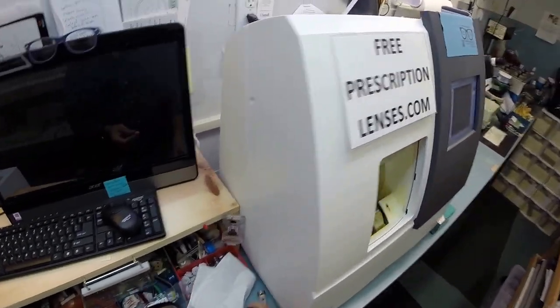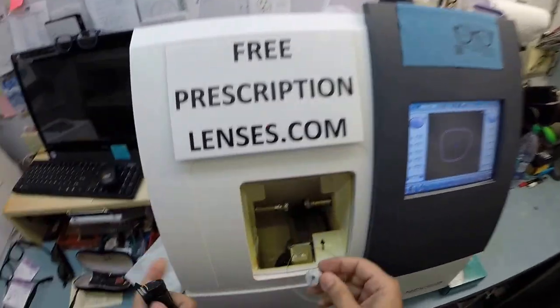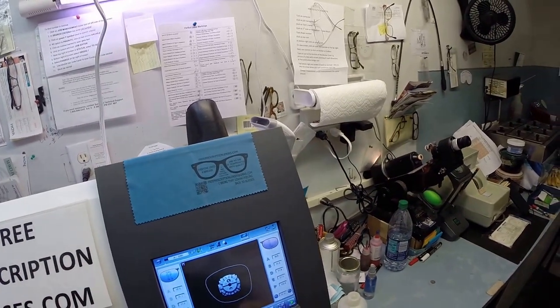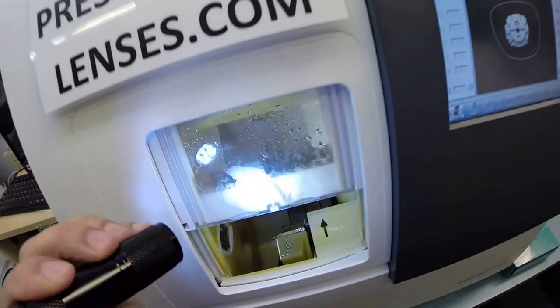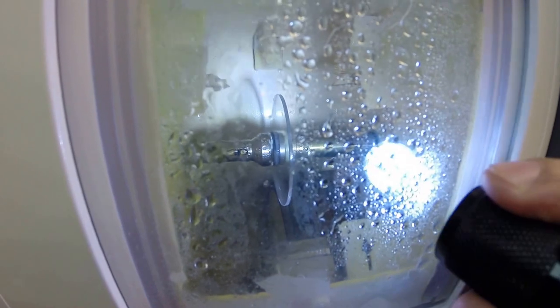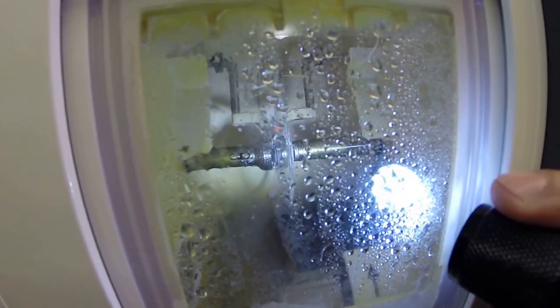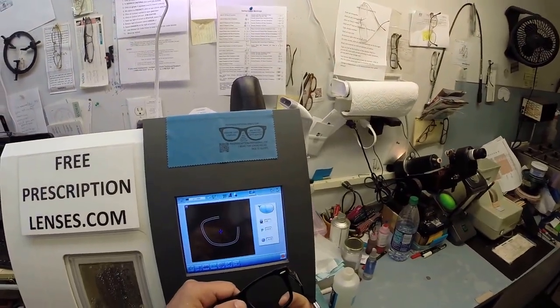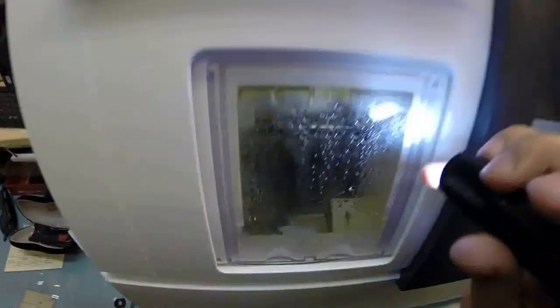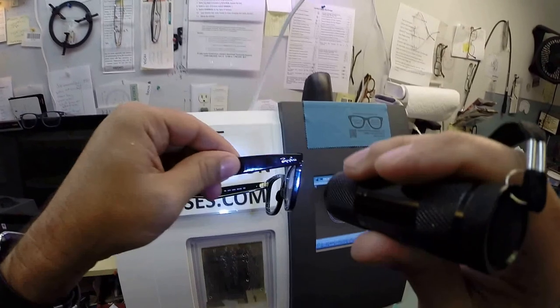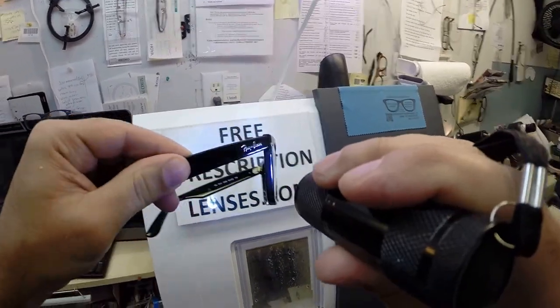We're going to put the lens back into the spot. Flip that over to L. And we're going to hit the green button, which again is start. The two white styluses are going to come back out, and it's going to trace the shape of the frame. Of course, you can see as it's measuring, going around, making sure that it's large enough to fit, and then measuring the thickness of the lens at every point to know exactly and precisely where to place the bevel, although you will have no edge thickness whatsoever because these are non-prescription.